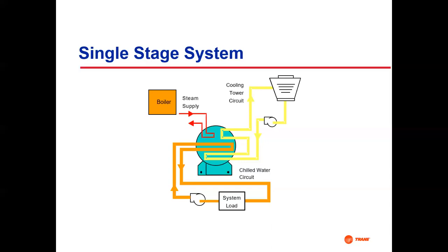It's going to provide the cooling that we need to operate the cycle. So our cooling tower is out here. We come out of the bottom of the cooling tower at 85, our design spec. We've got a little pump on it, pumping down through here. This is the absorber, where that exothermic reaction is giving off heat. We've got to cool it down. So we're 85 in, 95 out.